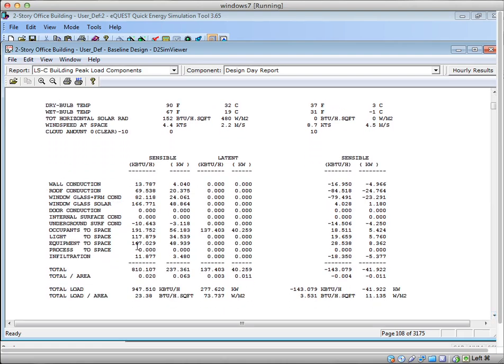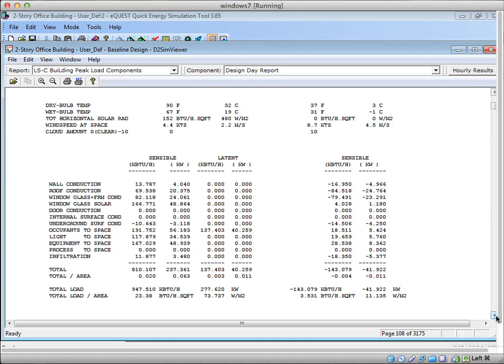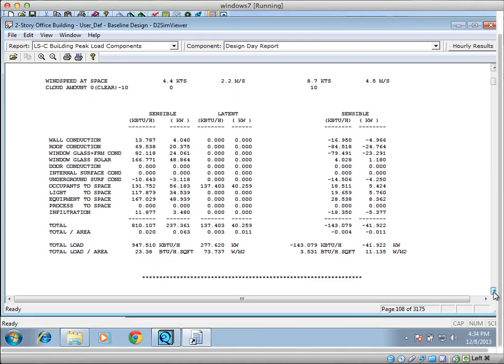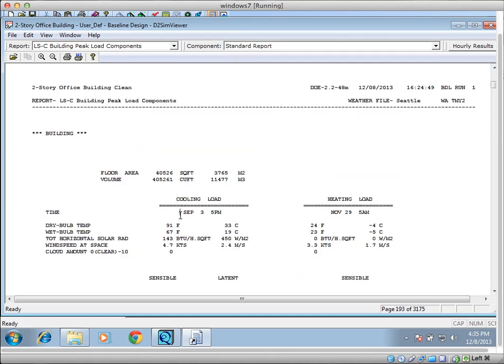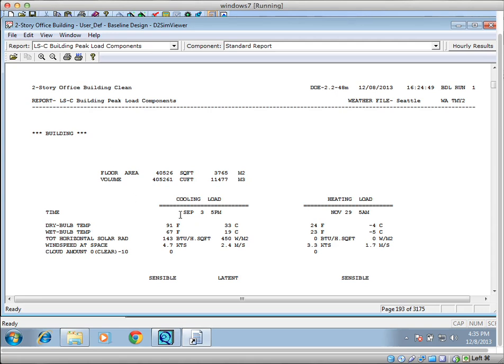And it breaks down all the loads into the space. The wall, the roof, heat, the windows, different things like that. This does not include the ventilation load, just to point that out. A little warning at the bottom. And here's the heating day as well. So if you wanted to see what the weather file peak was, you can actually look at standard report. And here, now we can actually see in the weather file, it actually found a peak at September 3rd. And that dry bulb peak was at 91 degrees.